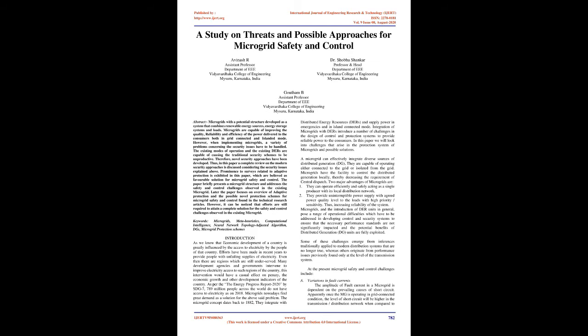Microgrids have the facility to control the distributed generation locally, thereby decreasing the requirement of central dispatch. Two major advantages of microgrids are: 1. They can operate efficiently and safely, acting as a single producer with its local distribution network. 2. They provide uninterruptible power supply with an agreed power quality level to the loads with high priority or sensitivity, thus increasing the reliability of the system. Microgrids, and the introduction of DER units in general, pose a range of operational difficulties which have to be addressed in developing control and security systems to ensure that the necessary performance standards are not significantly impacted and the potential benefits of distributed generation, DG, units are fully exploited.